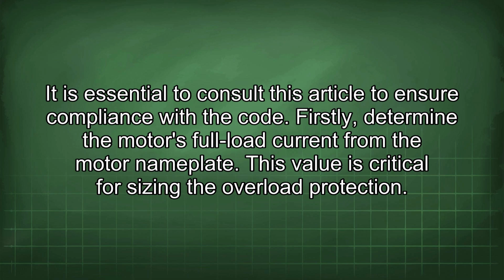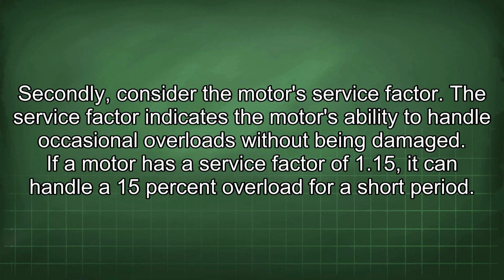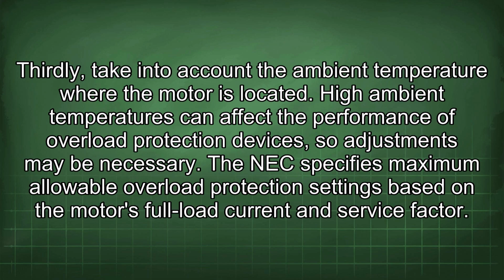Firstly, determine the motor's full load current from the motor nameplate. This value is critical for sizing the overload protection. Secondly, consider the motor's service factor. The service factor indicates the motor's ability to handle occasional overloads without being damaged. If a motor has a service factor of 1.15, it can handle a 15% overload for a short period. Thirdly, take into account the ambient temperature where the motor is located. High ambient temperatures can affect the performance of overload protection devices, so adjustments may be necessary.